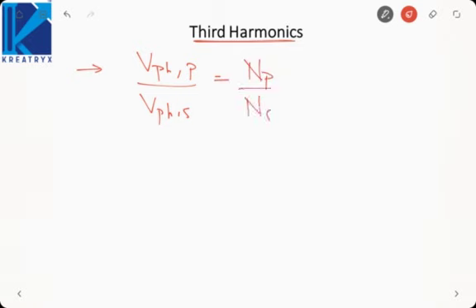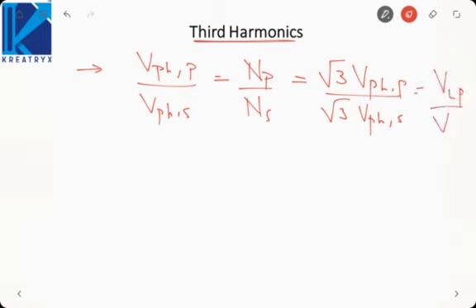Now let us find some features first of all for the star-star transformer. If I take V phase primary by V phase secondary, this will be N primary by N secondary. This can also be written as root 3 V phase primary by root 3 V phase secondary, that is VL primary by VL secondary. So as in a delta-delta connection, here also the line-to-line voltage ratio is same as phase-to-phase voltage ratio. Because root 3 will get cancelled out, so line voltages ratio will be same as phase voltage ratio.